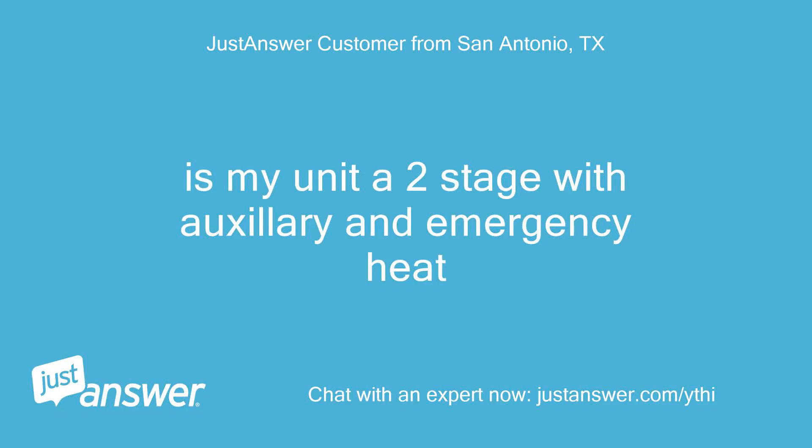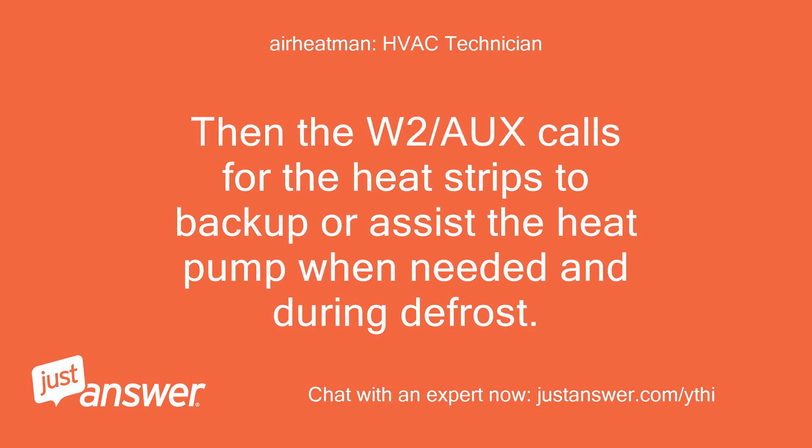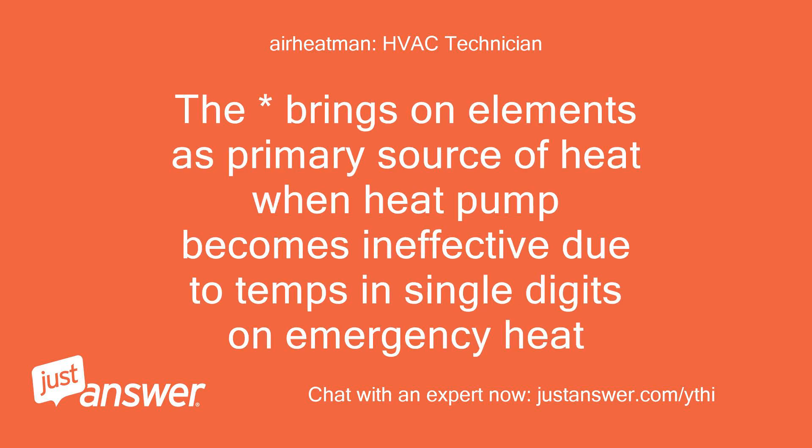Is my unit a two-stage with auxiliary and emergency heat? Yes — if there is a Y1 and Y2, that means the compressor is two-stage. The W2/AUX calls for the heat strips to back up or assist the heat pump when needed and during defrost. On emergency heat, it brings on the elements as the primary heat source when the heat pump becomes ineffective due to temps in the single digits.